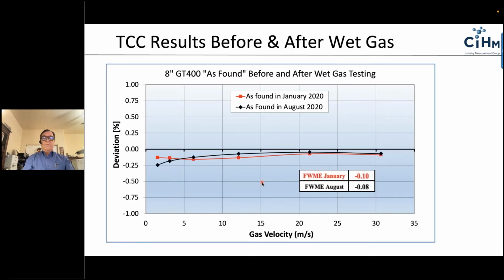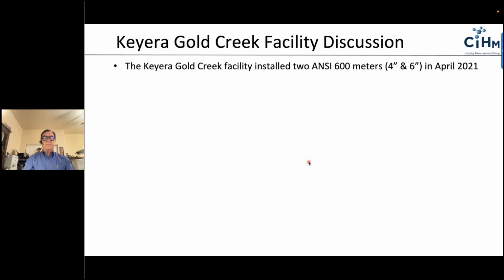So here are the results before and after. Wayne likes to calculate a thing called a flow weighted mean error. So if we take a look at the January test data, the red line here is a flow weighted mean error of about 0.10. This is essentially like a single meter factor that's discussed in OIML R137, which tells you how to calculate this. It kind of looks like a single meter factor for the entire flow rate range. The flow weighted mean error on the retest was 0.08, essentially a difference of 0.02 between these two curves, which is what I would consider inside the reproducibility and the repeatability of both the meter and the facility.